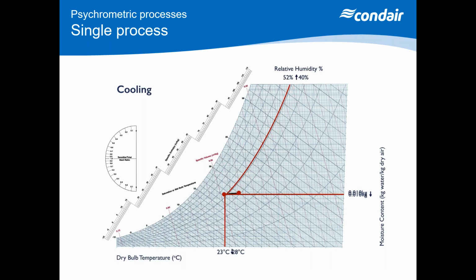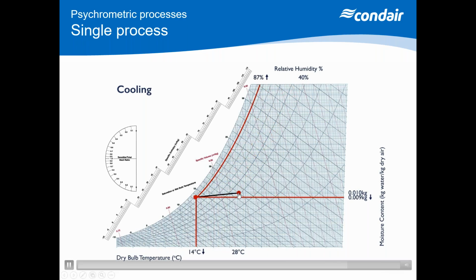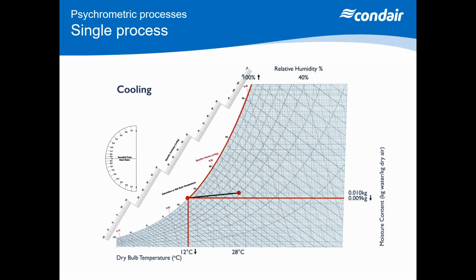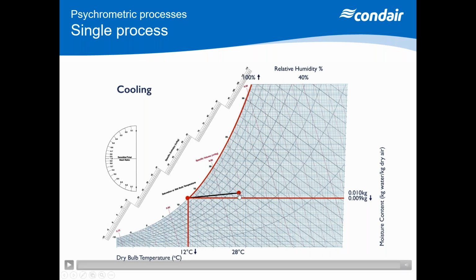If I'm mechanically cooling, I could see a right to left process line such as this. And the effect here is that we see a decrease in dry bulb temperature. We'd expect to see that because we're cooling. But we also see an increase in relative humidity. There's 40, 50, 60, 70% RH. But even though we're seeing an increase in relative humidity, I could be seeing a reduction in moisture content if I'm doing any latent cooling.